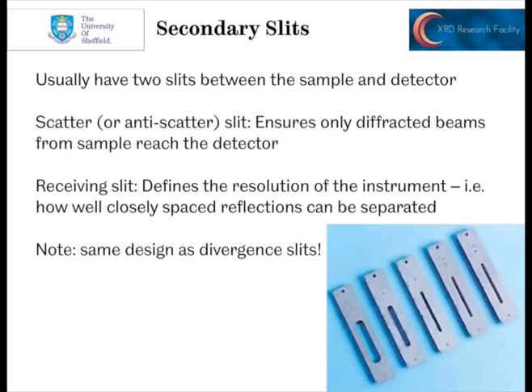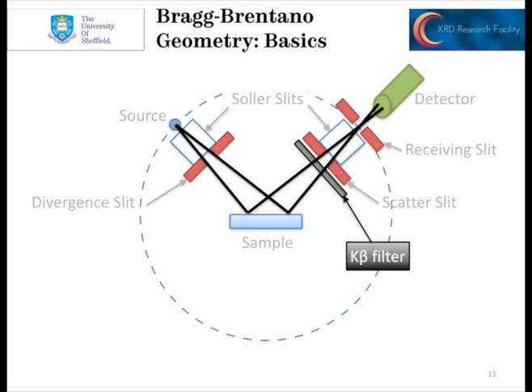For secondary slits, we usually have a scatter slit, which ensures only beams diffracted from the sample reach the detector so we're not getting beams coming from elsewhere in the machine. We also have the receiving slit, placed at the focal point — it defines the resolution of the instrument, how well closely spaced reflections can be separated. Note the design is exactly the same as the divergence slit. The final aperture to look at is the K-Beta filter, which tends to be exactly the same design as the slits but with a piece of metal foil — we covered those in the last video.